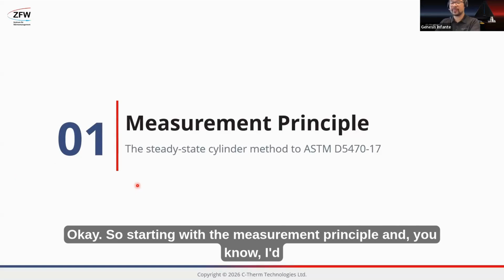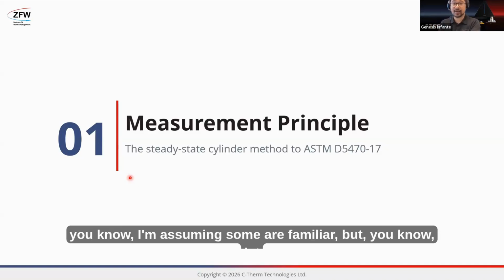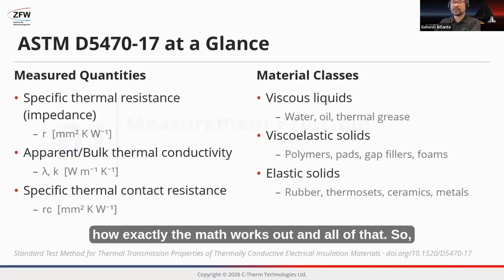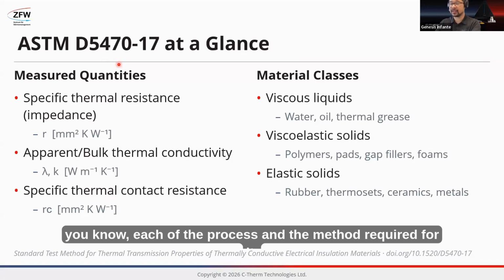Okay, so starting with the measurement principle, I'd like to go over it as quickly as possible, and I'm assuming some are familiar, but let us know if you'd like to get more details down the road on how exactly the math works out. So, as mentioned earlier, the TIM tester works according to the D5470 ASTM standard, describing the process and the method required for it.